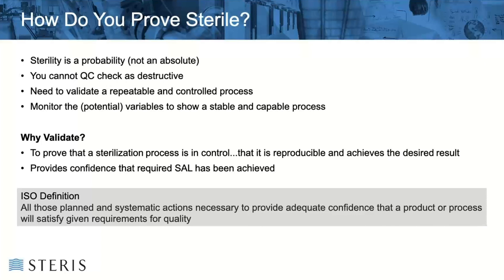Sterility assurance is a probability, and we cannot quality control test devices as that entails the destruction of valuable medical devices. Therefore, we need to validate a stable and repeatable process to demonstrate it's capable of consistently delivering the required microbiocidal inactivation. The routine sterilization process is subsequently a repeat of this validated process, where critical process parameters are measured to demonstrate repeatability. As shown in the ISO definition of validation, it's providing confidence that a controlled process satisfies the requirements for quality and does so consistently.